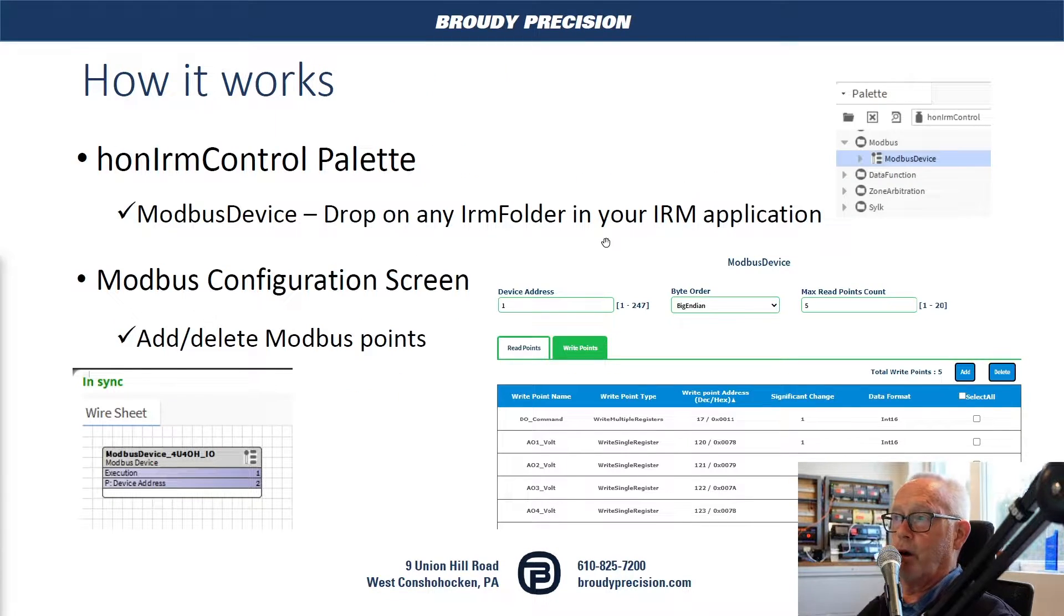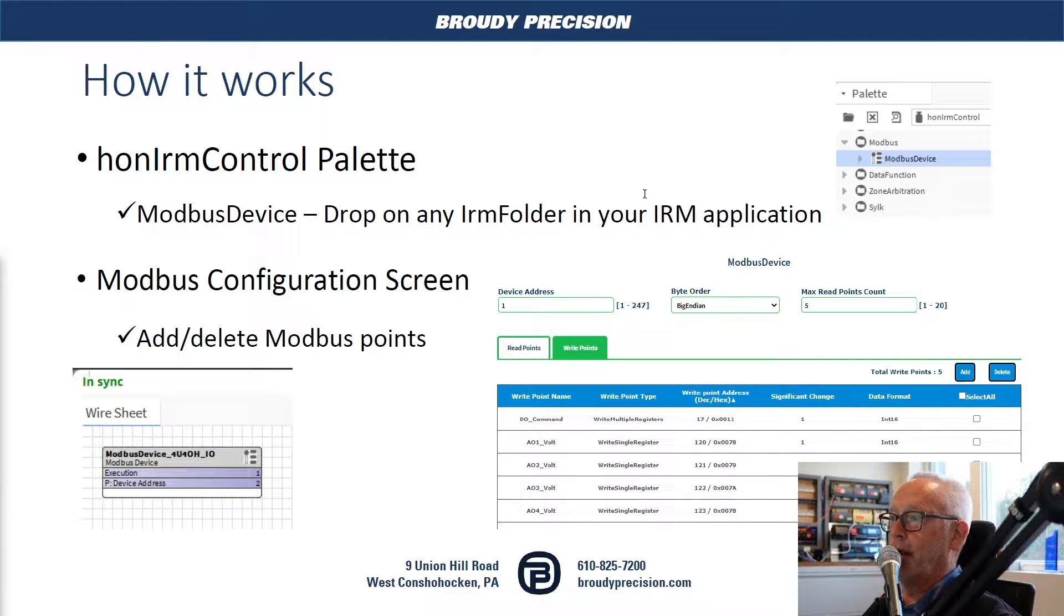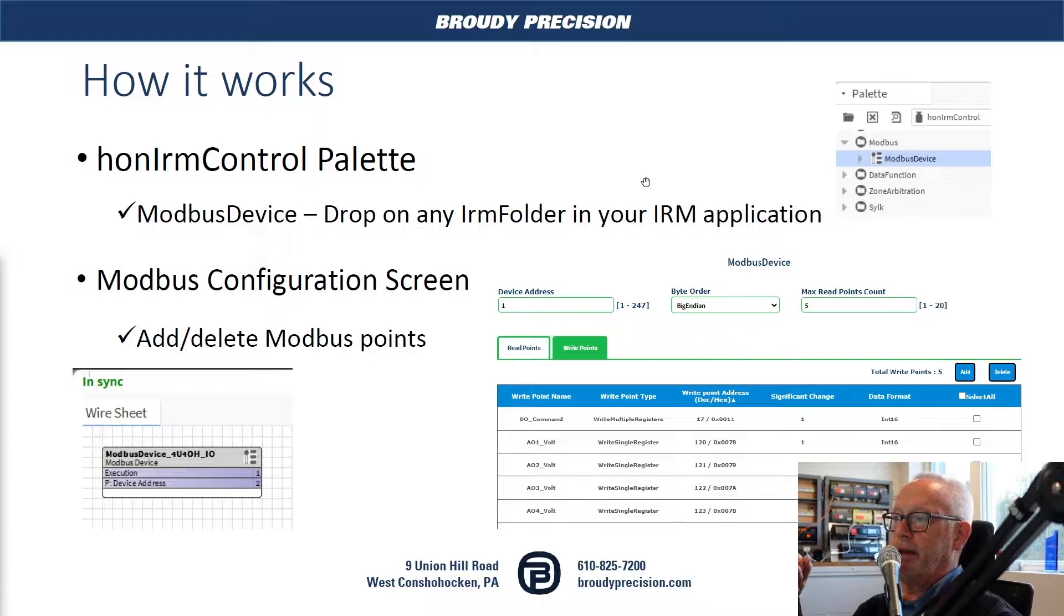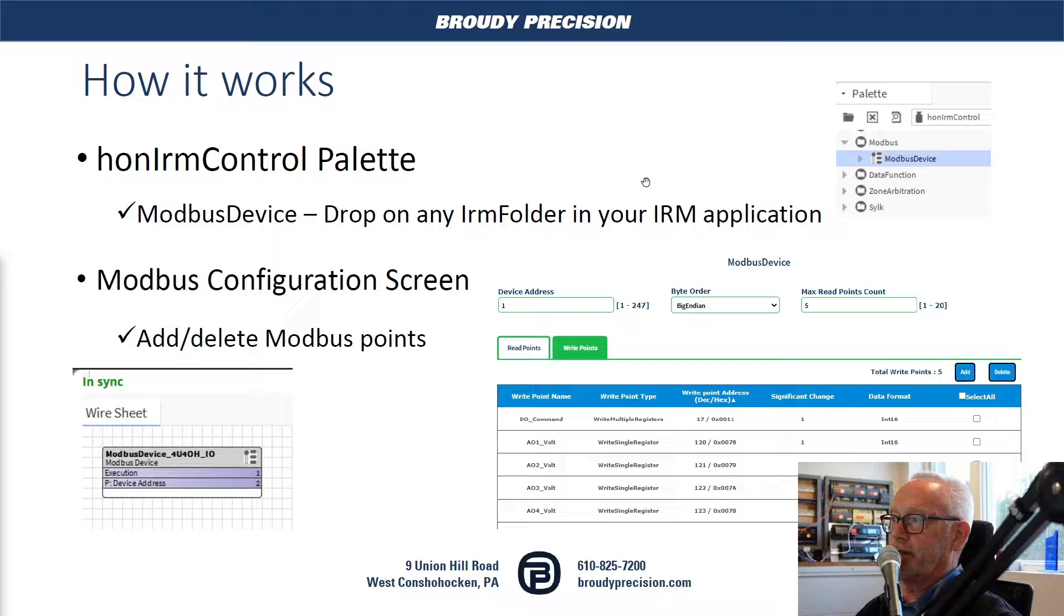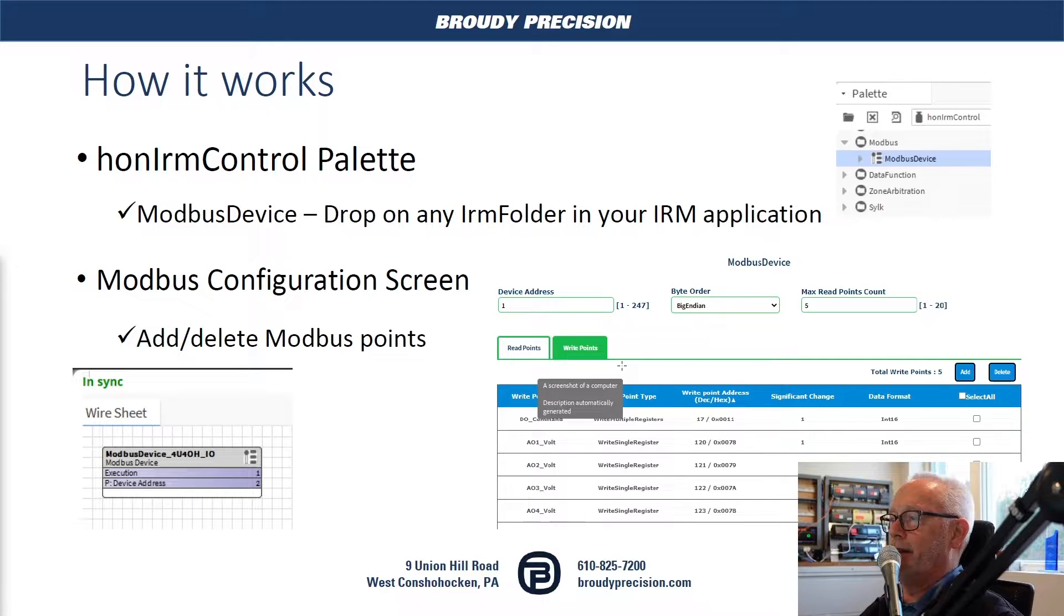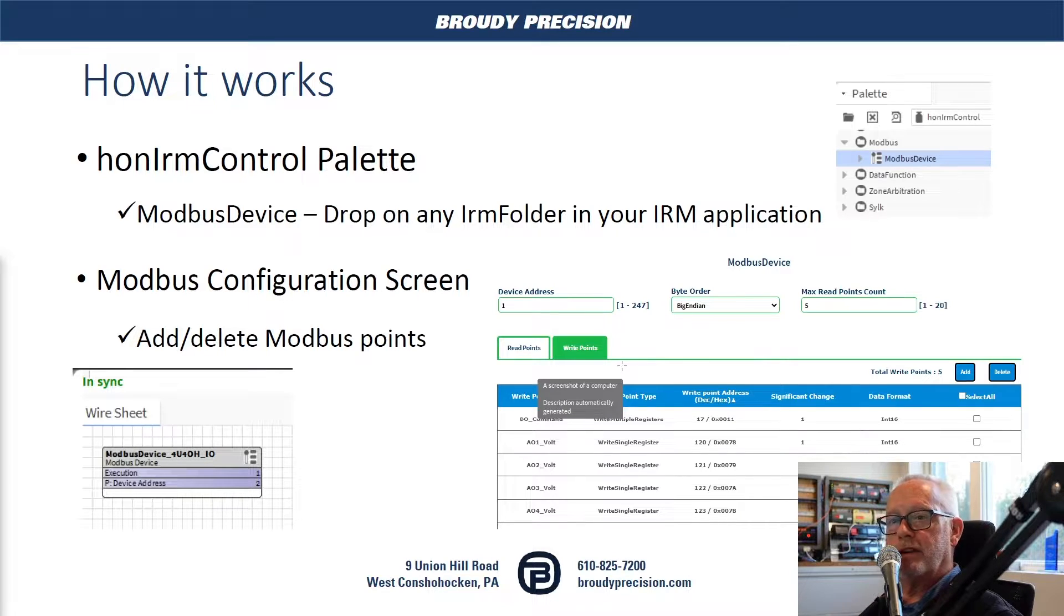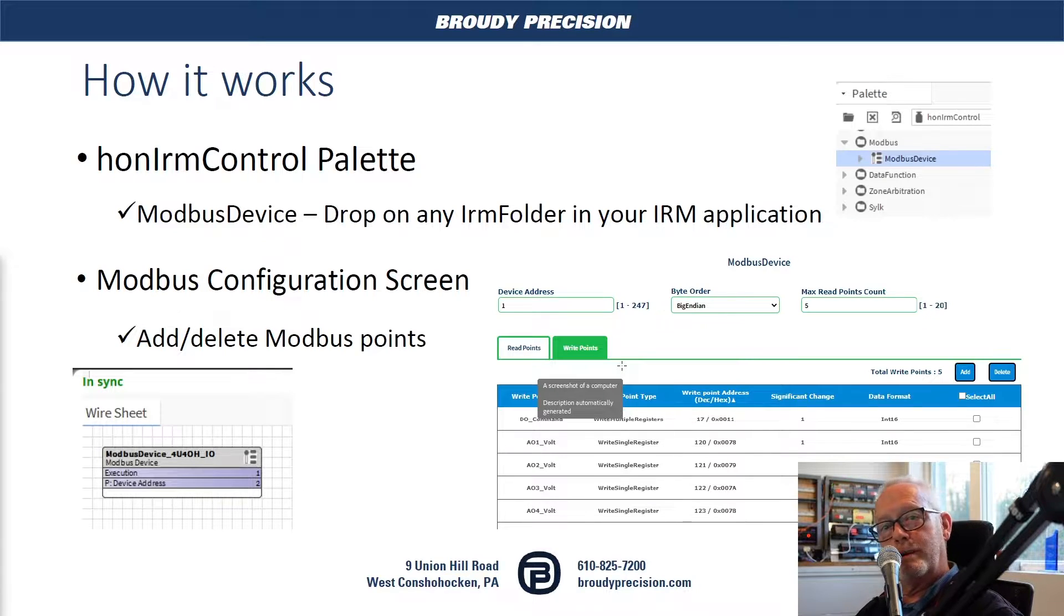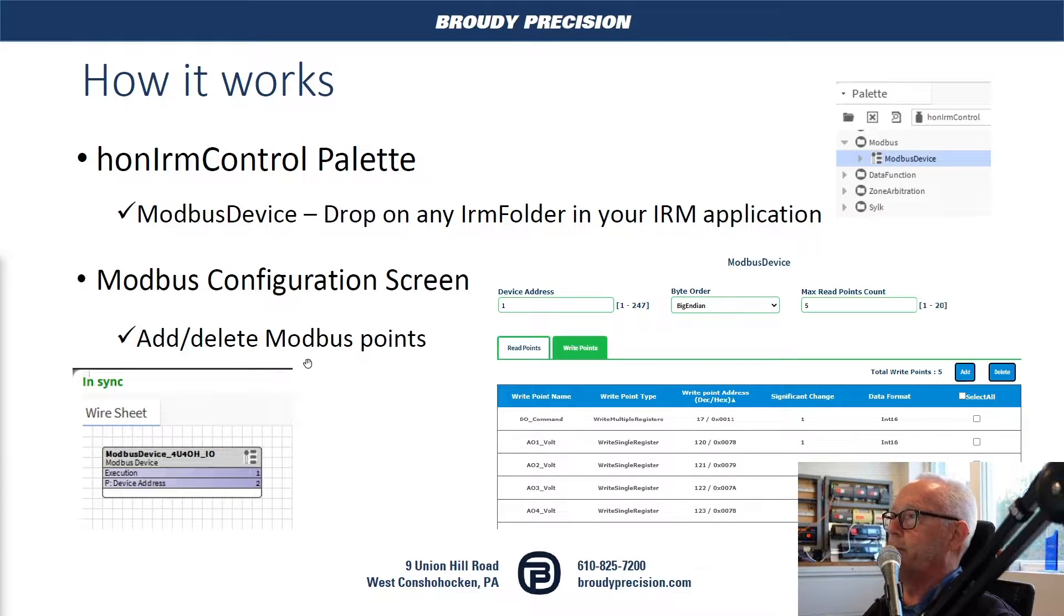How does it work? In the Honeywell IRM control palette, you're going to find a Modbus folder, and within there is a Modbus device. You're just going to take that device, drop it in on your application, and from there you'll be able to go to a Modbus configuration screen which allows you to add points, writable and read-only type points. Keep in mind, Modbus is not like BACnet. You do not have the ability to do any kind of discovery, so you need to have documentation available from the manufacturer.